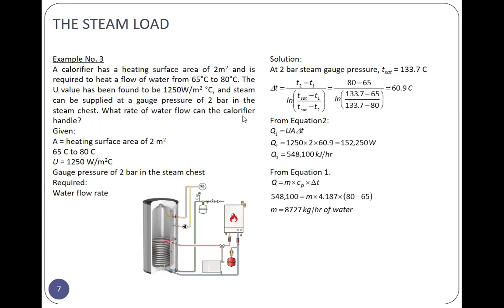So there is a design for the steam coil, and the steam can be supplied at a gauge pressure of 2 bar in the steam chest. What rate of water flow can the calorifier heat? So, given the heating surface, you have a design for your heat exchanger, and you can get its capacity. U is 1250 watts per square meter. It's like the earlier case, except only the coil is considered, not the wall of the tank, because that has a different value. So gauge pressure 2 bar in the steam chest. Required: the flow rate.